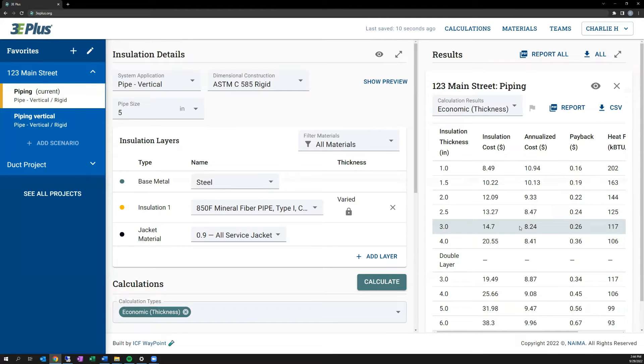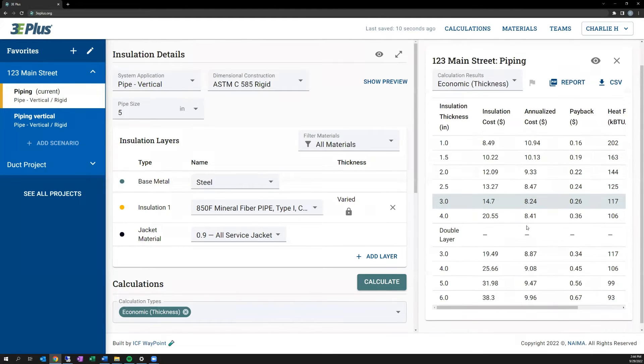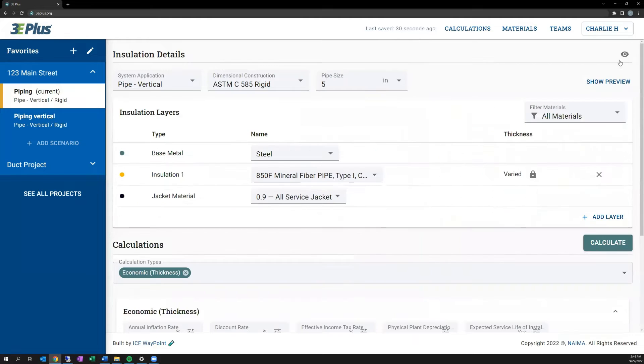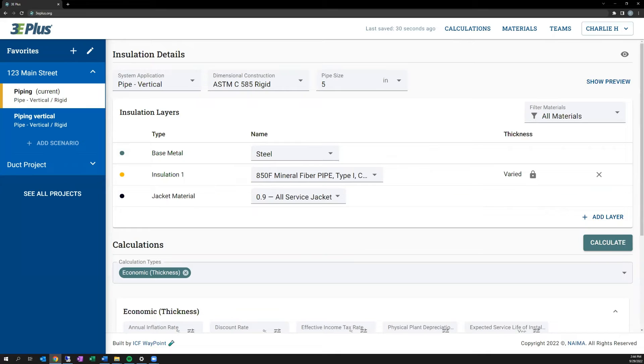In this case, it's three inches, a single layer that provides the best payback for the owner.